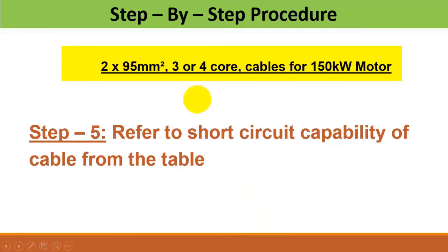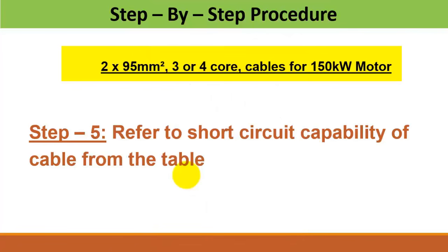for 150 kilowatt motor. The last step is to refer to short circuit capability table to check the maximum short circuit withstand capability of selected cable size. I hope you understand how to size the cable.